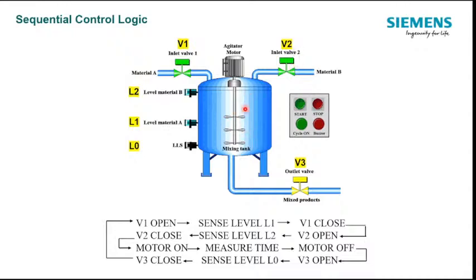I can use an external timer or the inbuilt timer feature of the PLC to monitor the time. For example, let's say half an hour. Once the half an hour is over, I can take that as an input to my PLC, and I will write a logic to stop the motor whenever I get an input from the timer. I will switch off this motor and open V3.